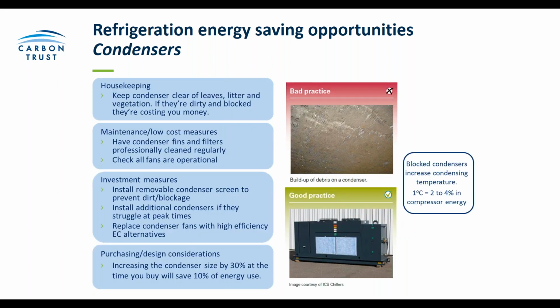So condensers are the next on the list. So this is where you need to make it really easy for the condenser to reject the heat. So find out where your condensers are and make sure that they're not dirty or blocked. If they are, they're costing you money. So make sure you keep the condenser, as they're usually external, clear of leaves, litter, vegetation, that kind of thing. So it's really important to inspect that.